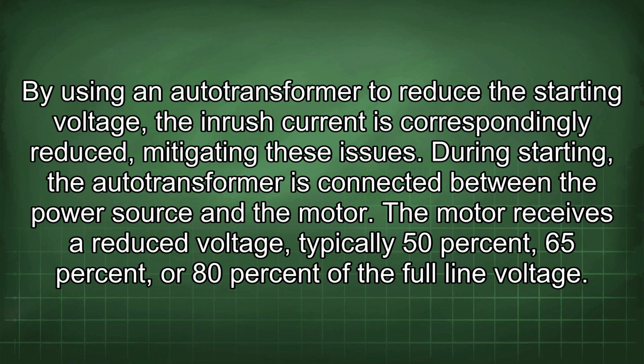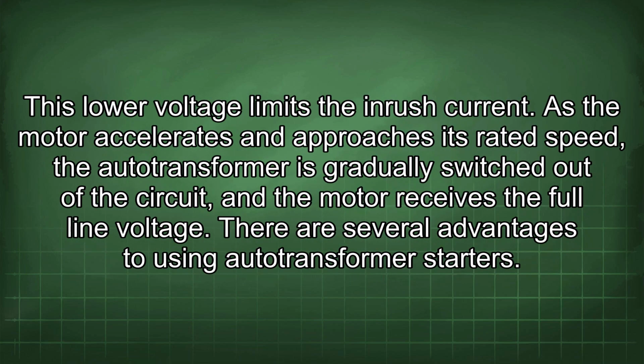During starting, the autotransformer is connected between the power source and the motor. The motor receives a reduced voltage, typically 50%, 65%, or 80% of the full line voltage. This lower voltage limits the inrush current. As the motor accelerates and approaches its rated speed, the autotransformer is gradually switched out of the circuit, and the motor receives the full line voltage.